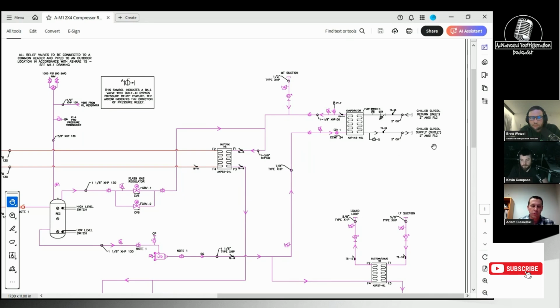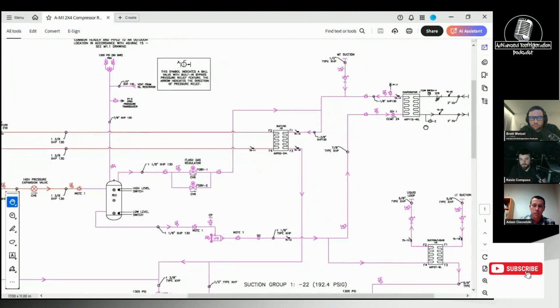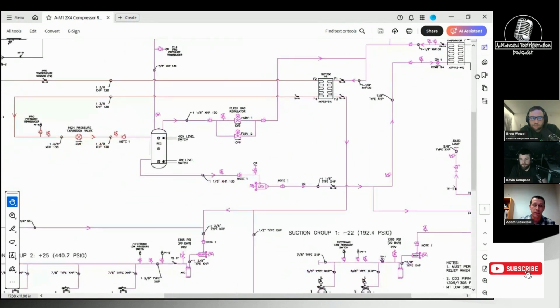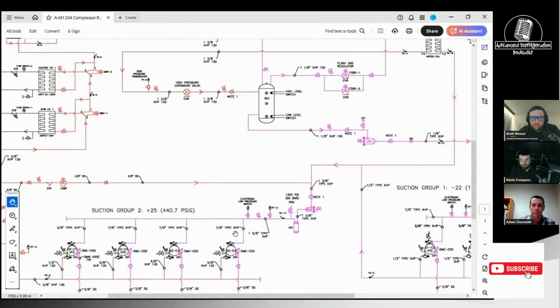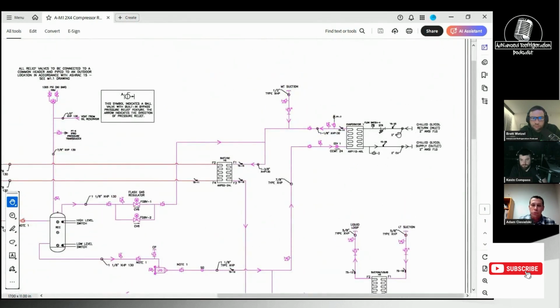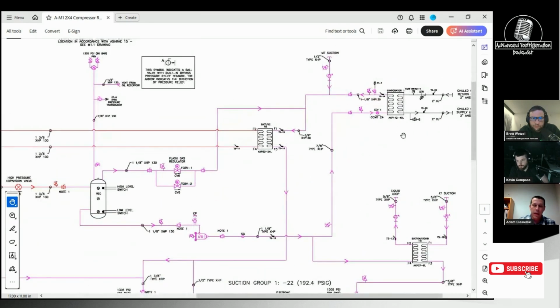During the winter time, the chilled water coils there's no load on them. They're actually in heating mode and not cooling mode. So this would satisfy set points, which is 75-80% of the load on the compressors. All my medium temp compressors would just shut off. Gotcha. So that ground loop, then what it does is we've got a recirculating pump, circulates the glycol through the ground loop and then dumps that warm water back into this loop. So it's artificially placing a load on this evaporator, and then that'll increase the load on compressors and run and give us some THR capability. Gotcha. So you have, I see two flash gas bypassers.